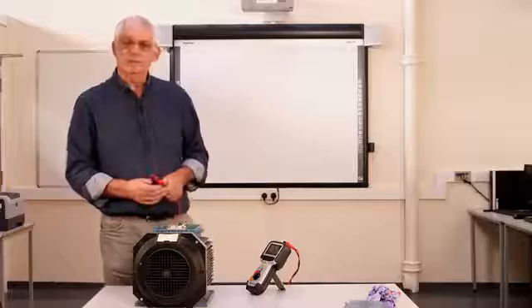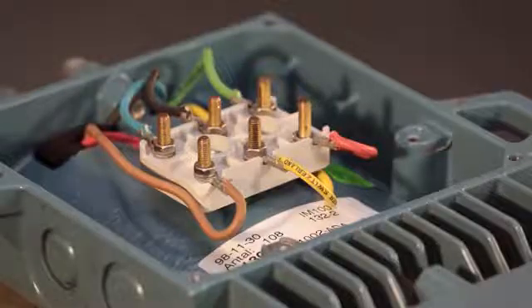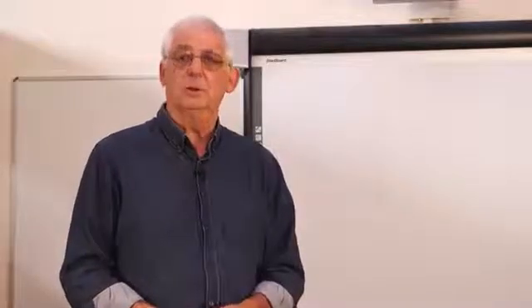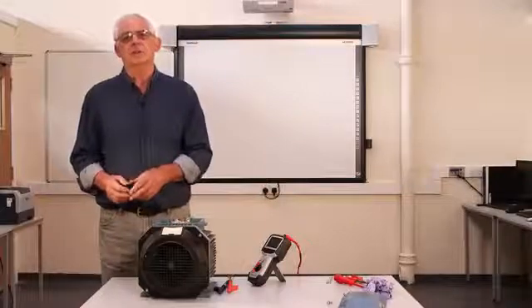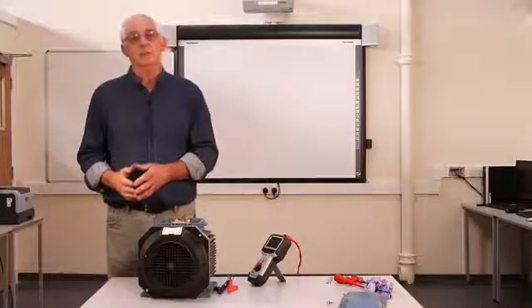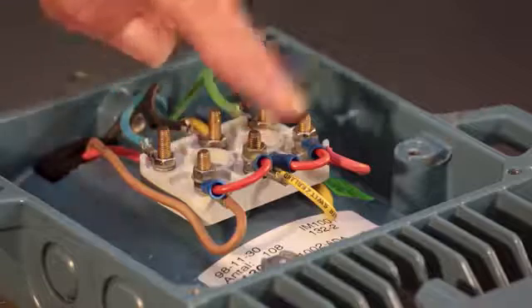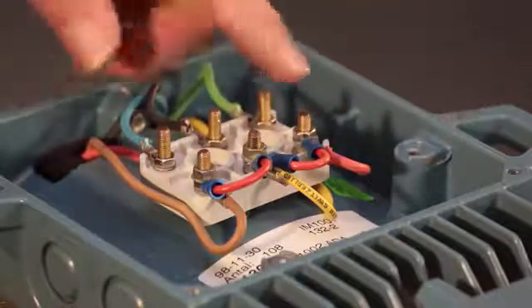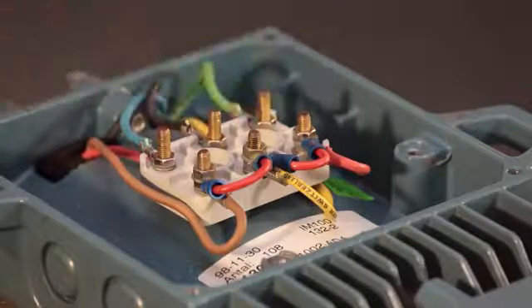Now what I need to do is connect the motor into star. If I wanted to connect this motor in delta, I would need to run six wires up to a motor starter. And inside the motor starter there's contactors that change from delta to star, which we'll look at in another video. If I want to connect a motor into star, all I need to do is find three ends of the windings and join them together. In the motor terminal block that's fairly easy because all I need to do is link either V1, W1, U1 together or could you even use V2, W2 and U2 together. Whichever way I do it, it really doesn't matter.